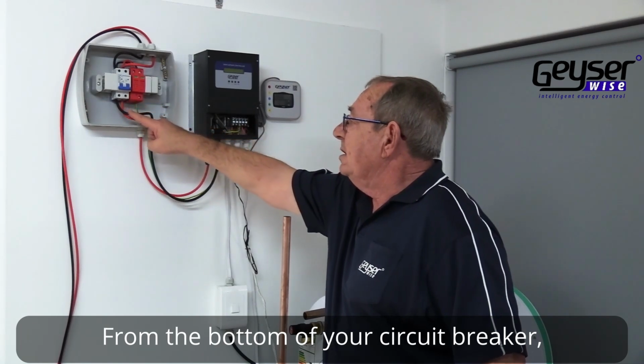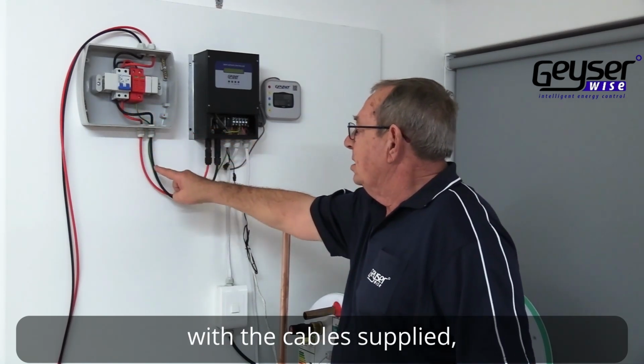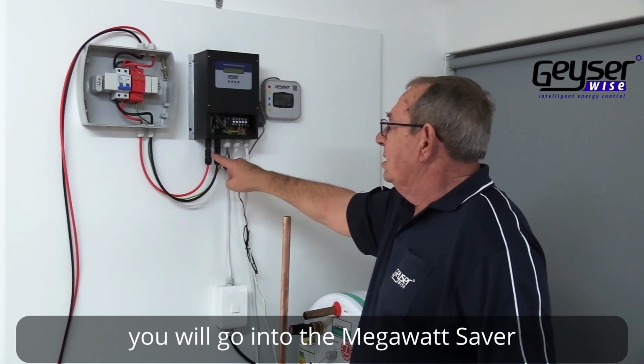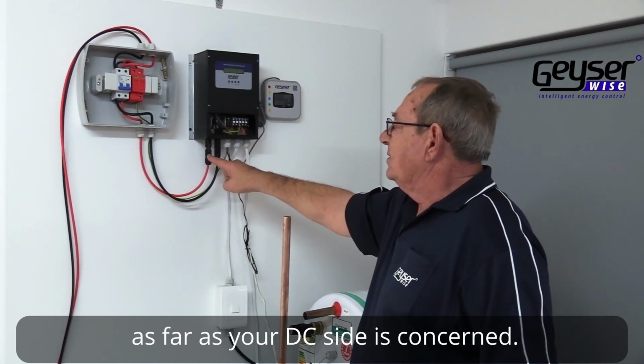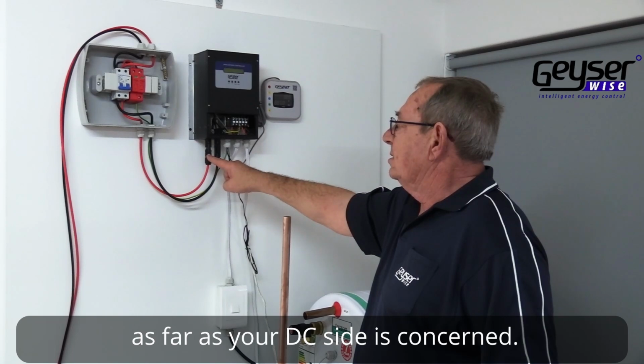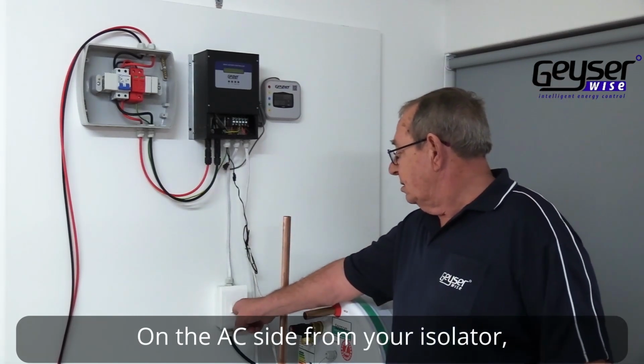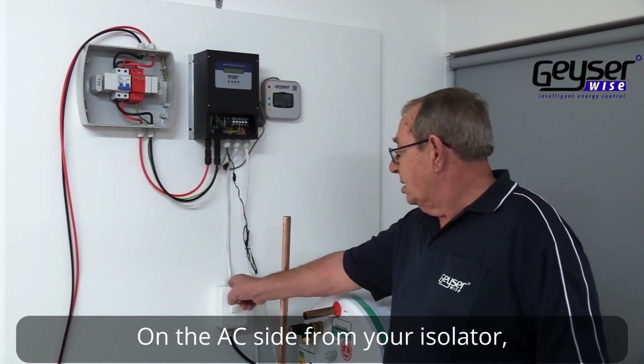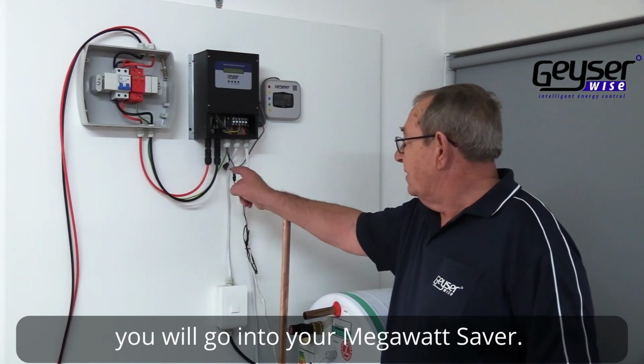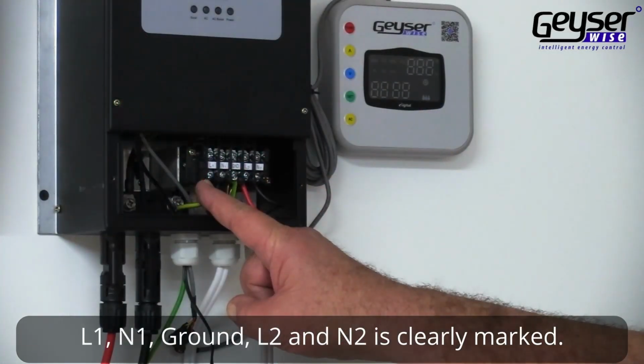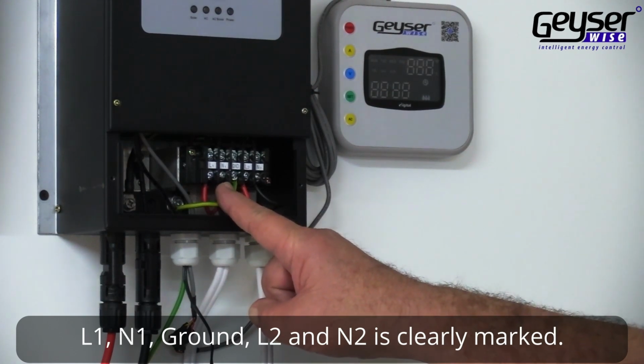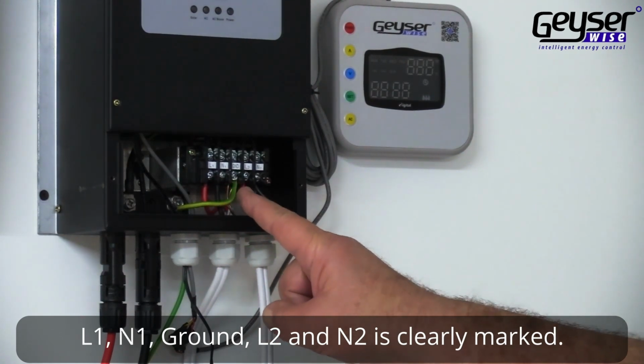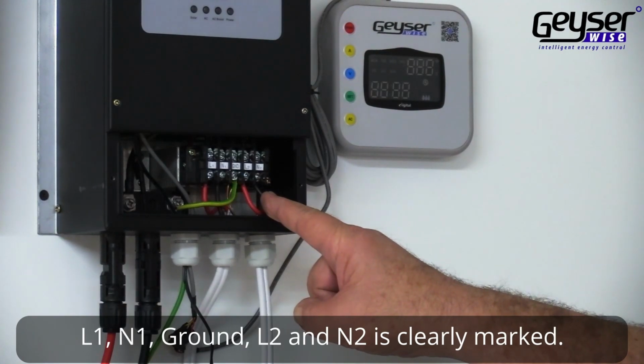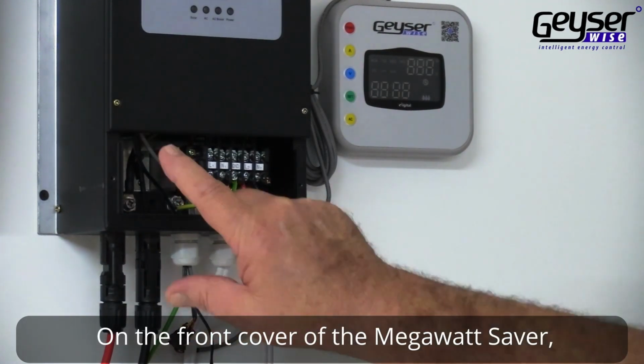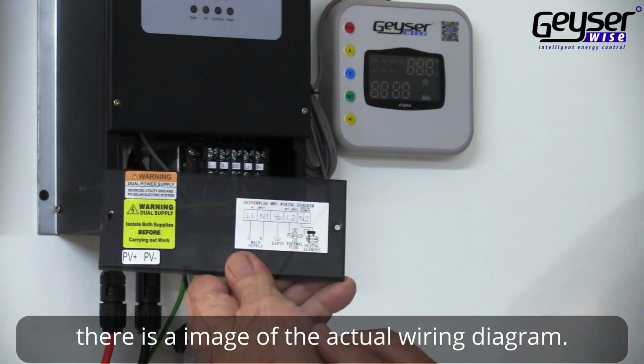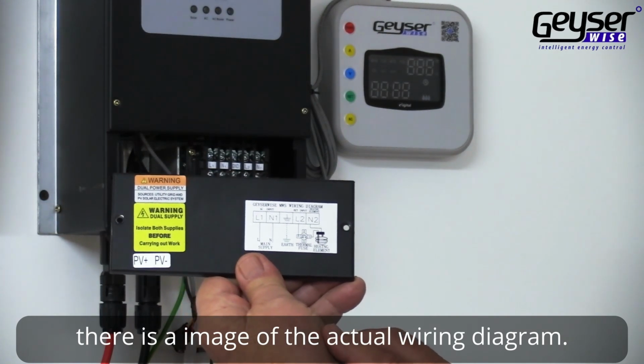Using the cables provided, the bottom of the circuit breaker must be connected to the Megawatt Saver as far as your DC side is concerned. On the AC side, your isolator must be connected to the Megawatt Saver. L1, N1, ground, L2 and N2 are clearly marked. Located on the front of the Megawatt Saver, there is an image of the wiring diagram.